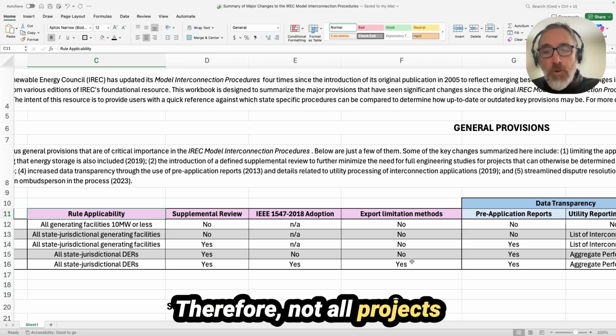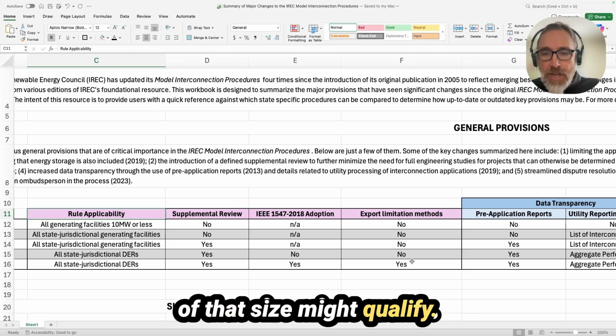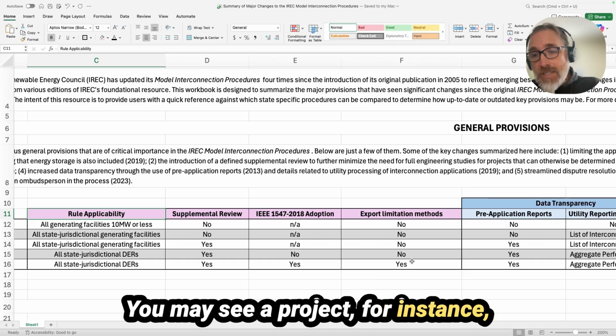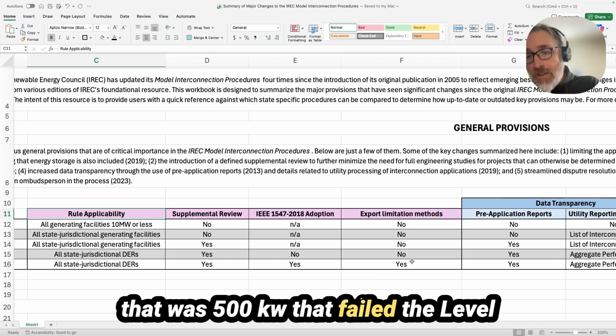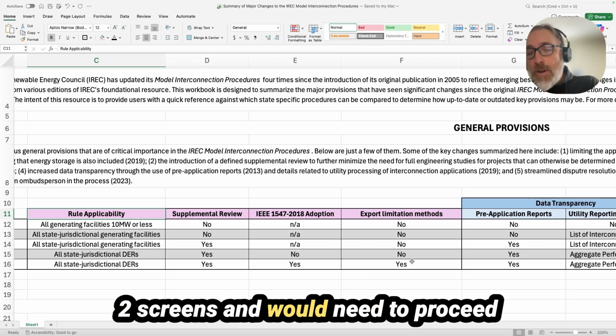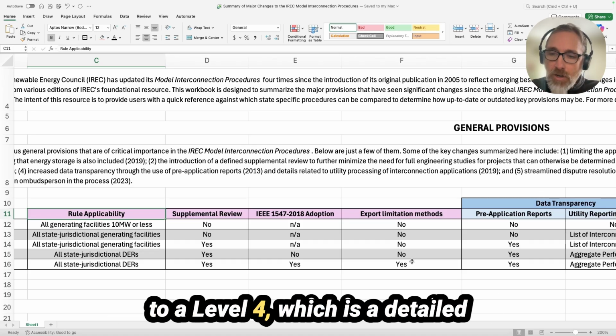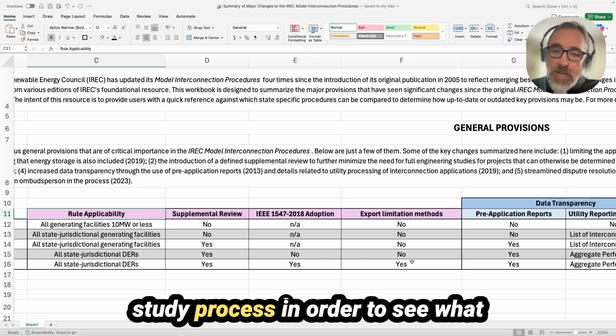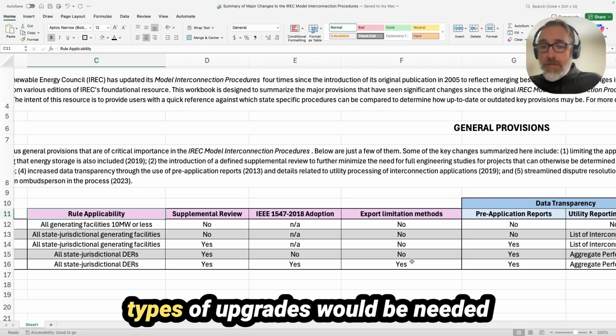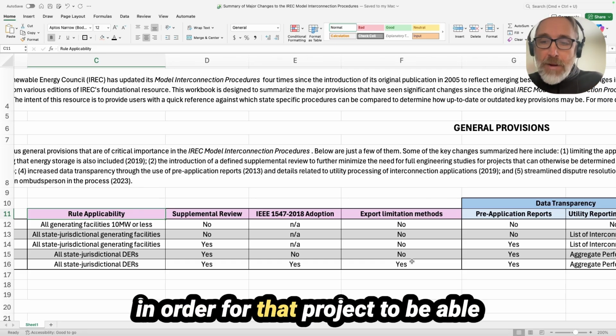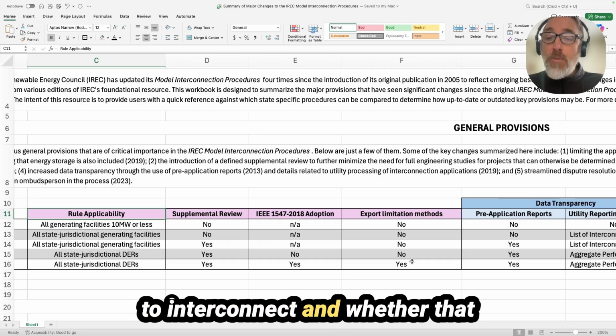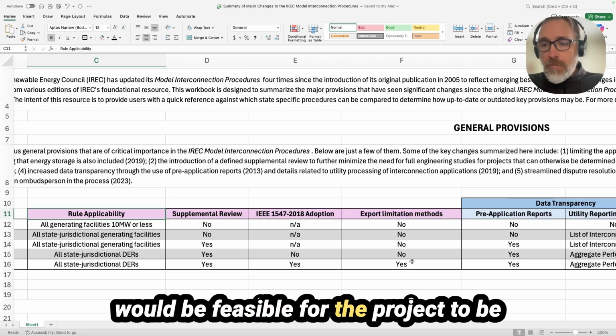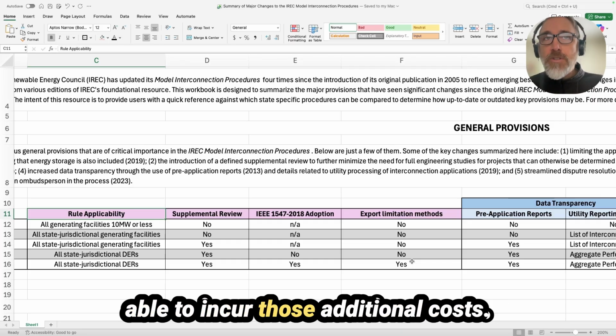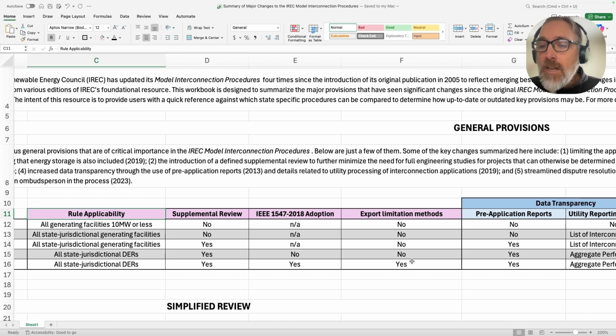Therefore, not all projects of that size might qualify. You may see a project, for instance, that was 500 kW that failed the level 2 screens and would need to proceed to a level 4, which is a detailed study process, in order to see what types of upgrades would be needed in order for that project to be able to interconnect and whether that would be feasible for the project to be able to incur those additional costs.